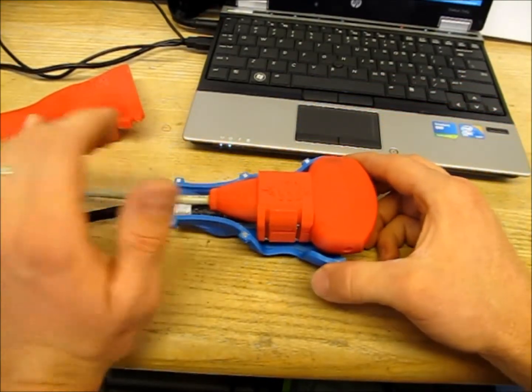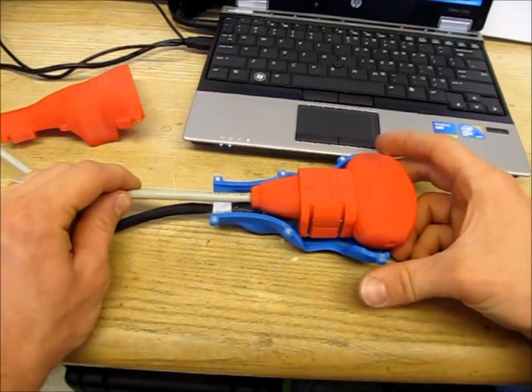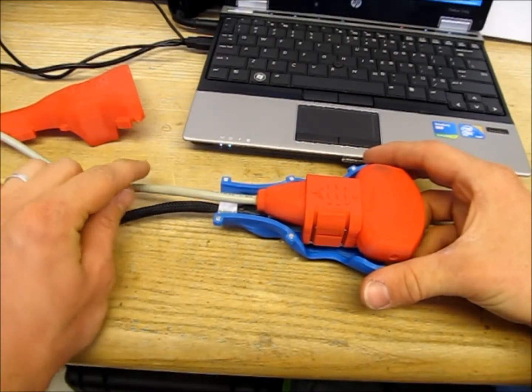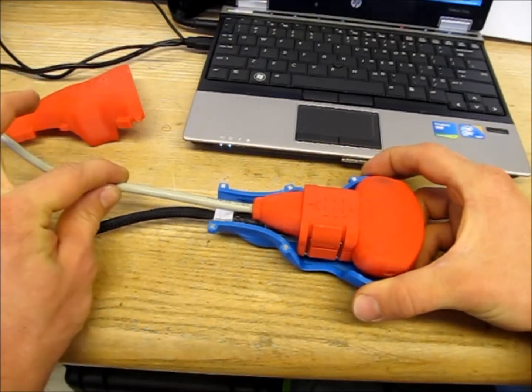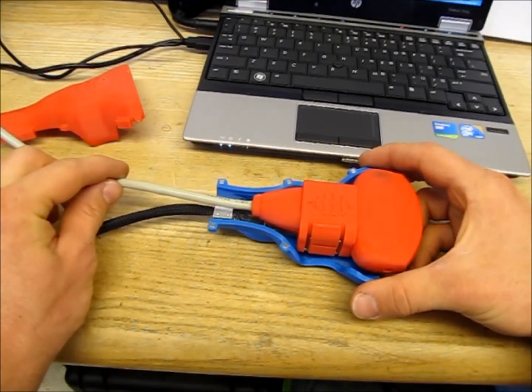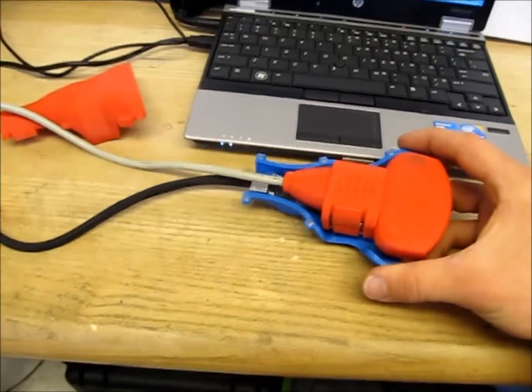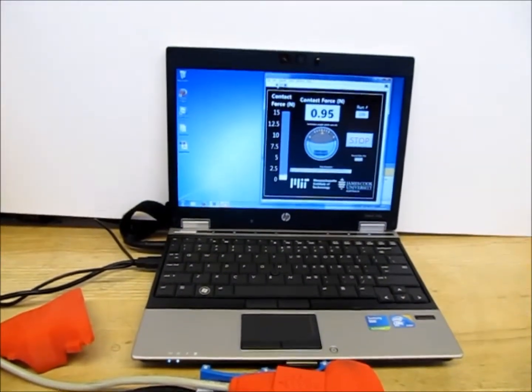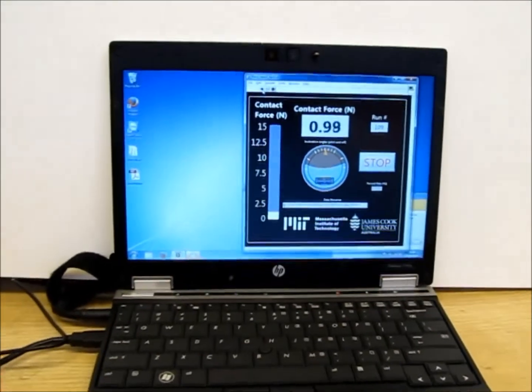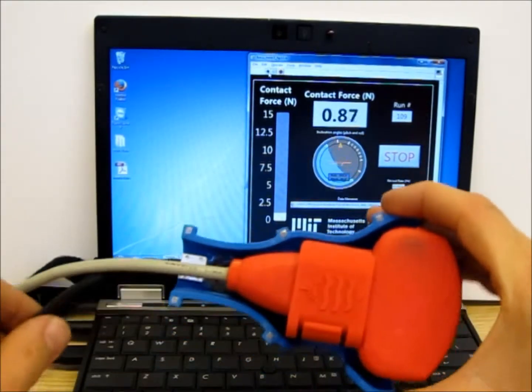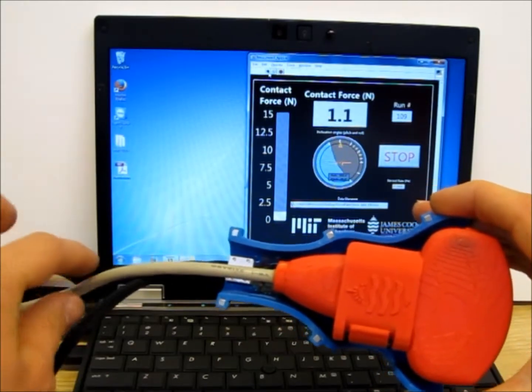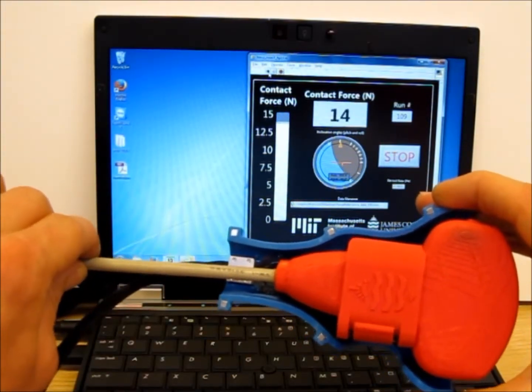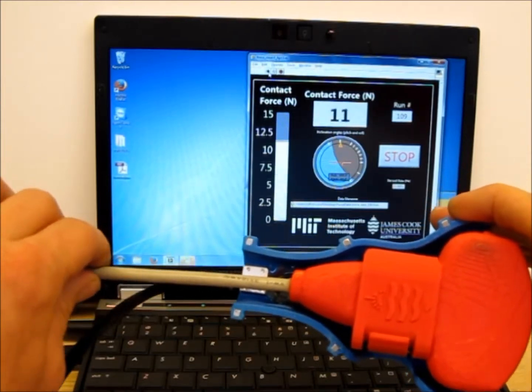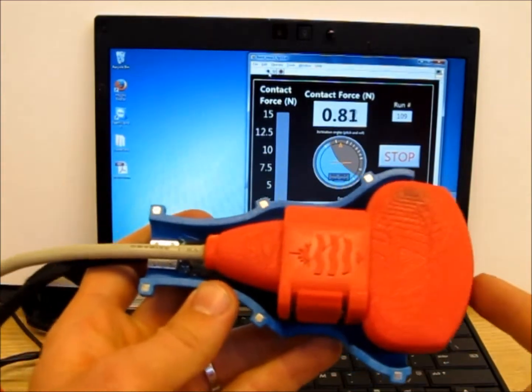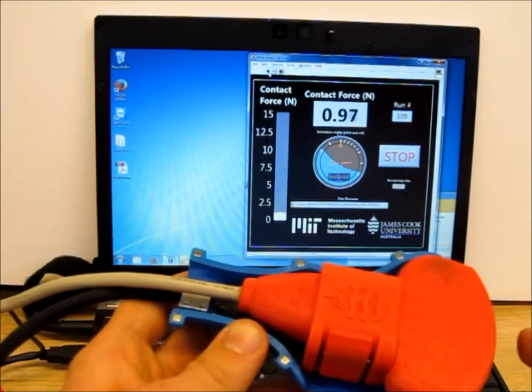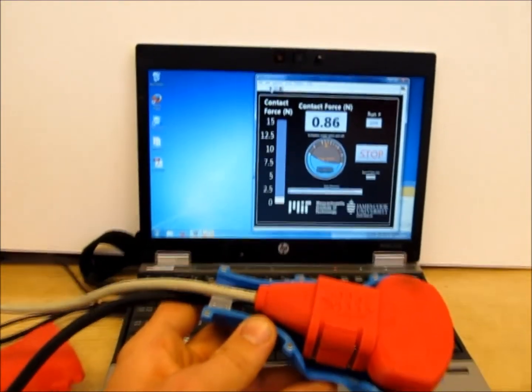The next thing we want to do is strain relieve the ultrasound cable here. The reason is that we don't want any tension applied to this ultrasound cable to show up as measured contact force. So let's take a look at the force gauge on the screen. Let me zoom in here. That's the current force reading. Now, in the current configuration, if we were to pull on the ultrasound cable, we see the force change. And we don't want that, because we want to measure the force that's applied to the ultrasound probe face right here. So we need to do what's called strain relieving.